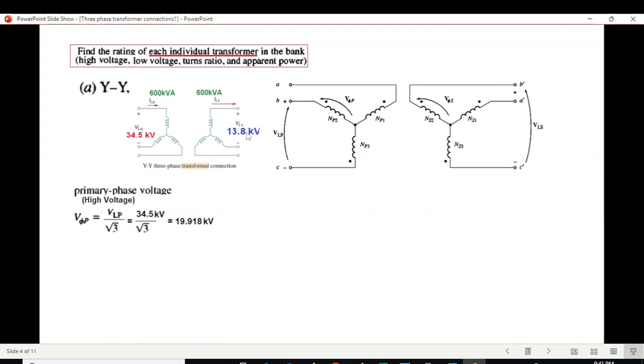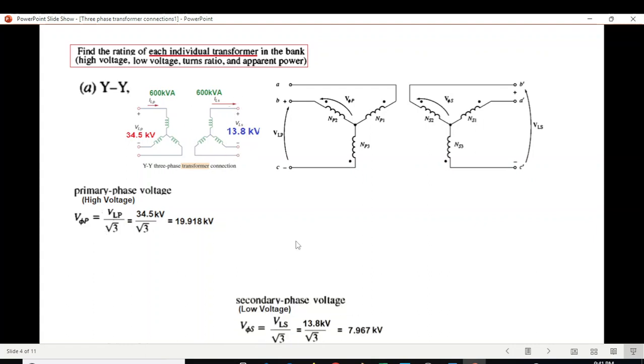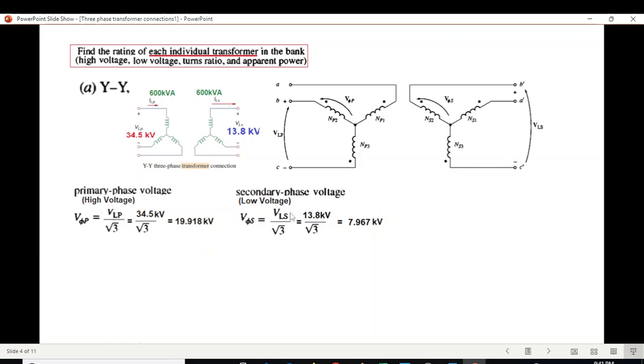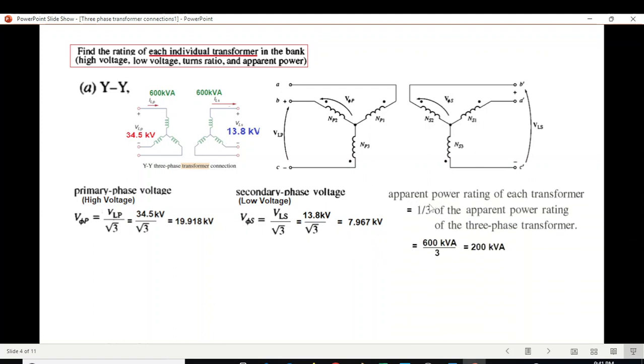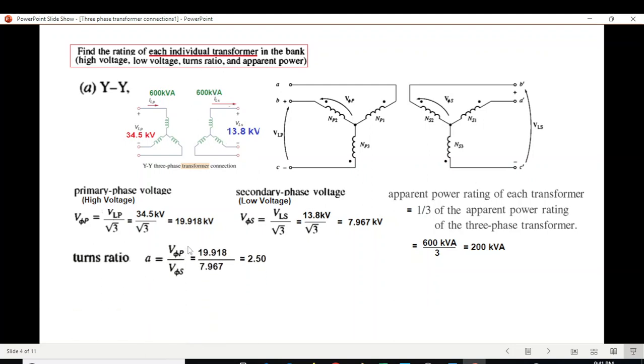Since the secondary is also Y-connected, we use the same formula: 13.8 divided by √3 gives the secondary phase voltage. Power per phase in a three-phase transformer is total power divided by 3, so power per phase is 200 kVA. The turn ratio is primary phase voltage divided by secondary phase voltage, giving a turn ratio of 2.5.